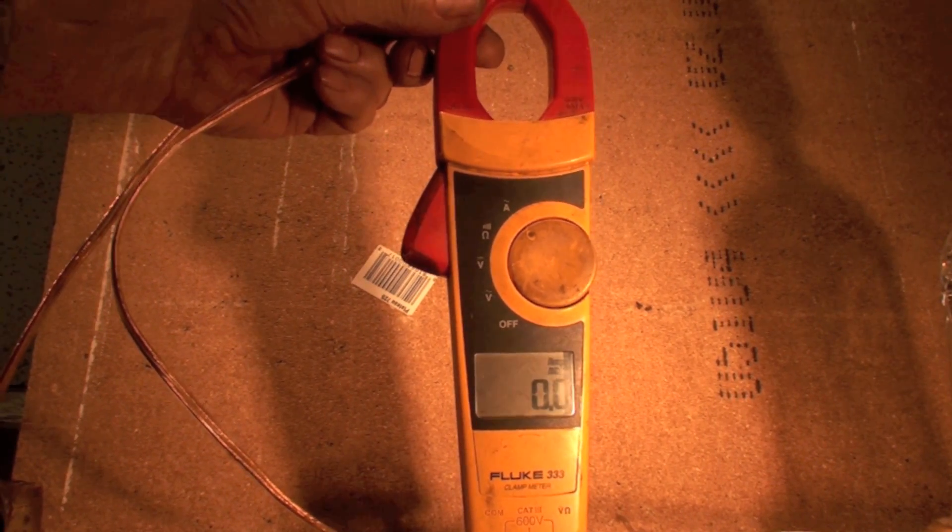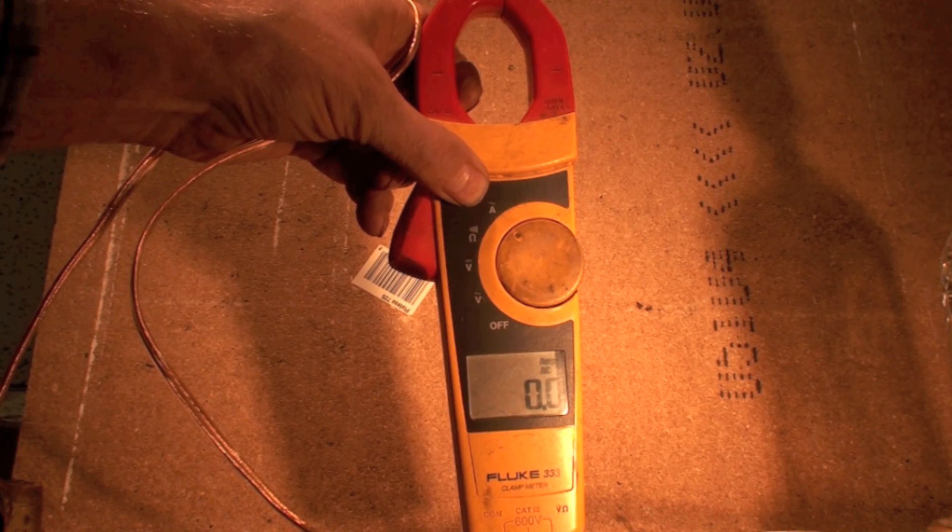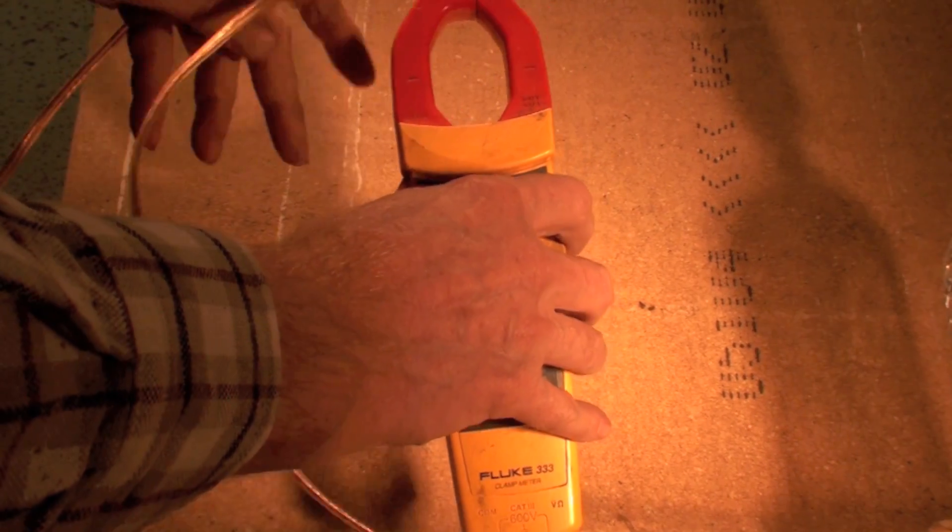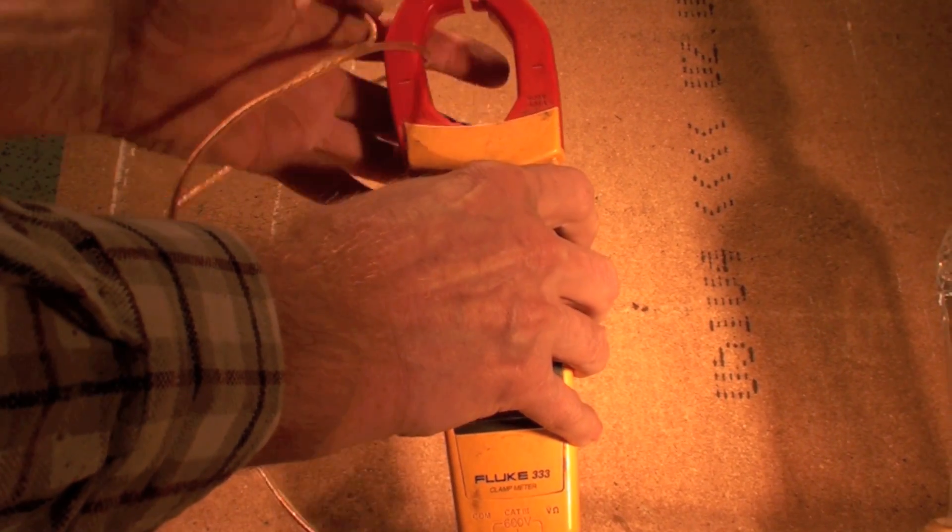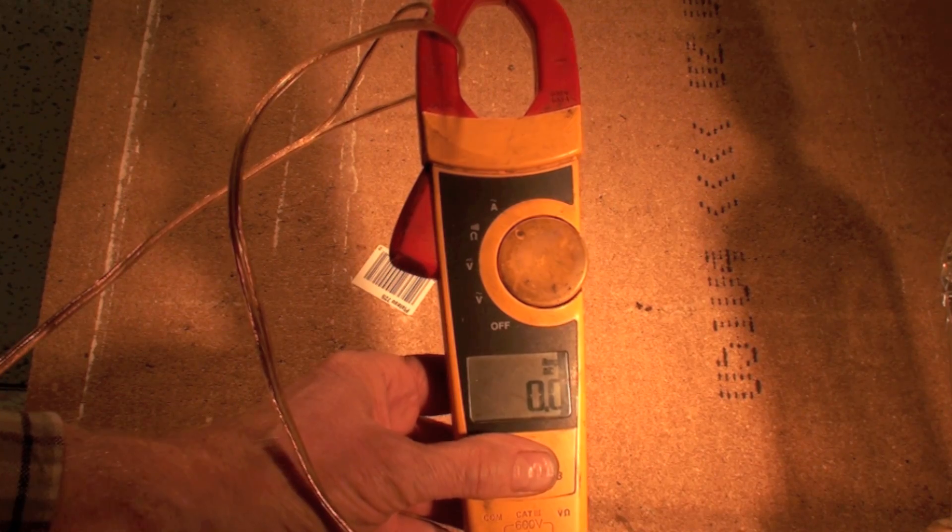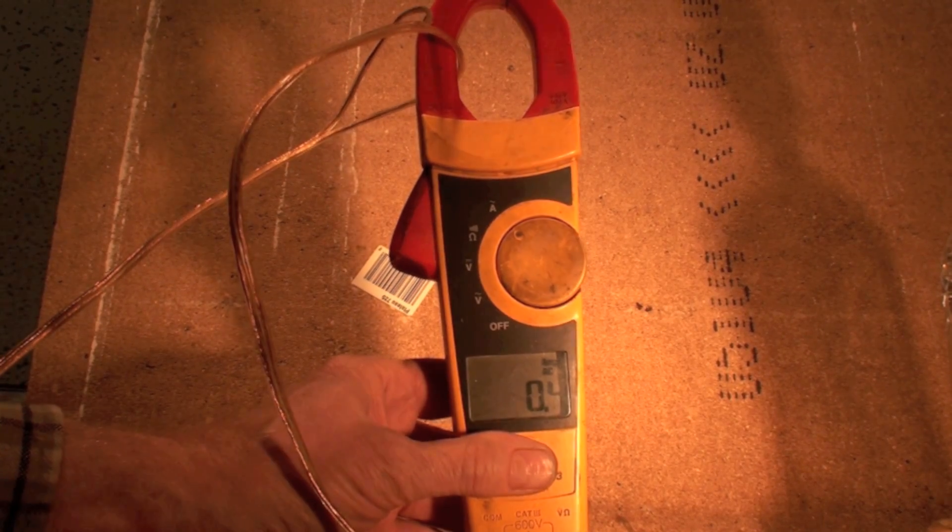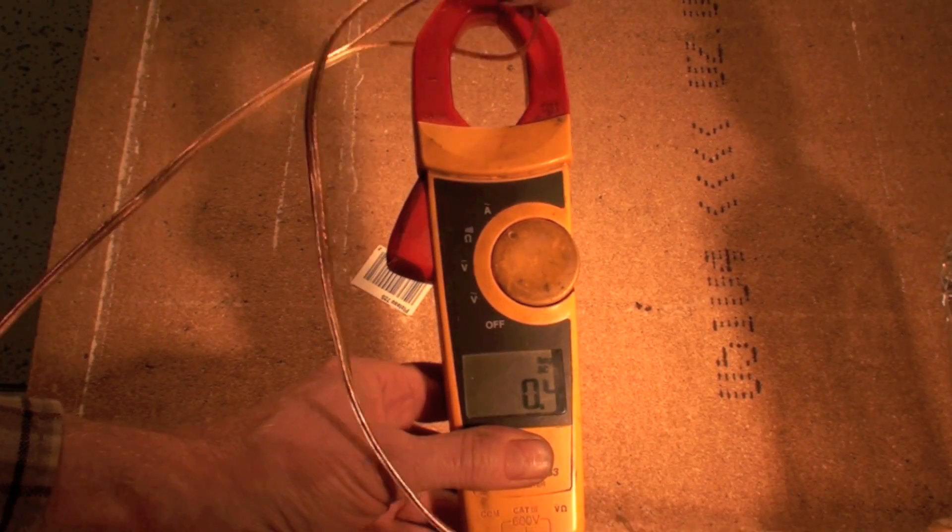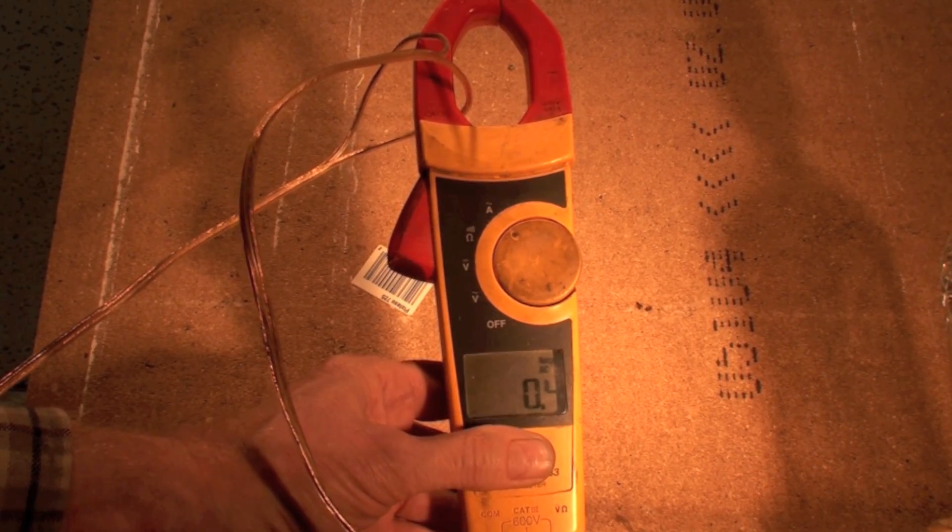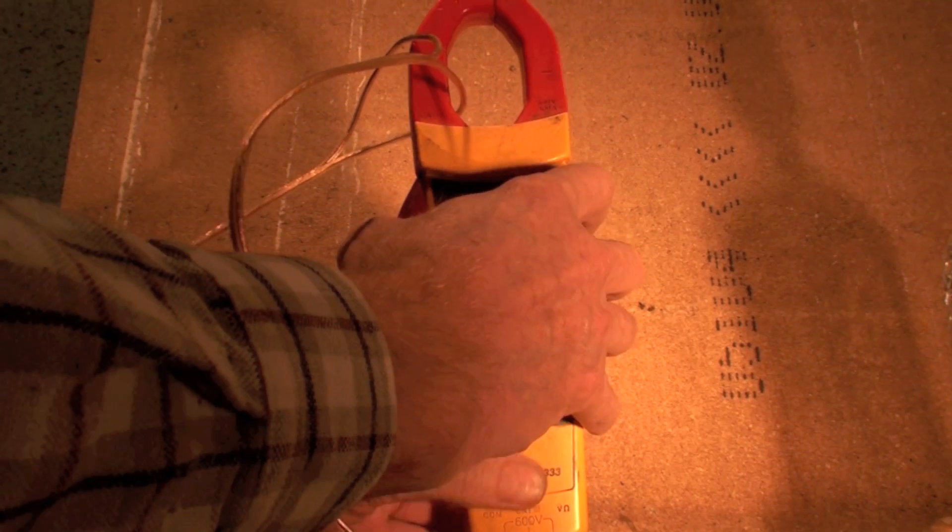Now we're going to check this thing in amps. We are in the amp position - that's A with a squiggly thing above, and that is for AC amps. It's reading zero, and I'm going to put one of these wires that's going to a lamp through here. If I turn the lamp off, it's still reading zero, but when I turn the lamp on, now it's reading 0.4 amps. I can move this around in here and it doesn't seem to make much difference as long as it's clamped on one wire. You can see 0.4 amps - I've got one wire clamped.